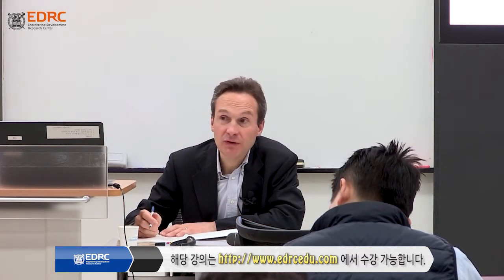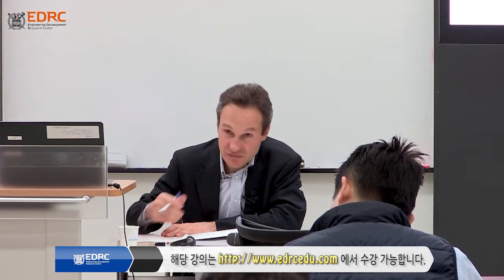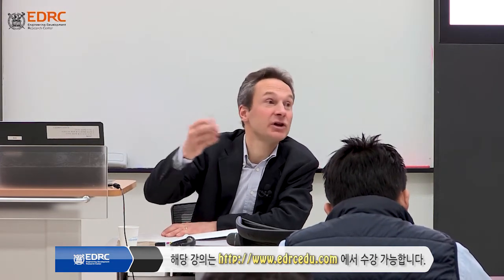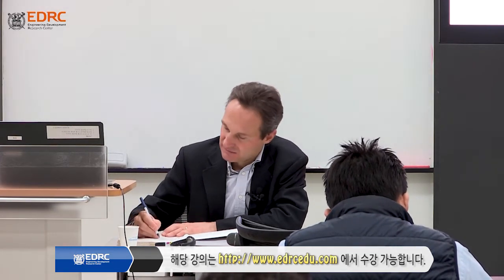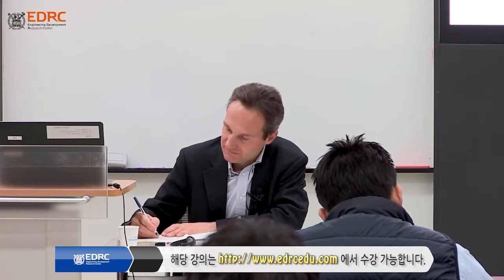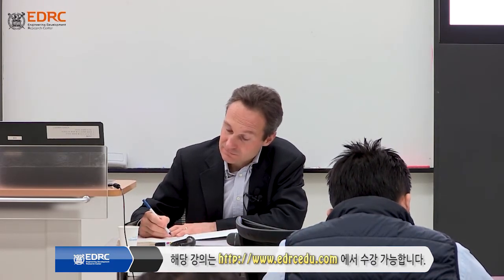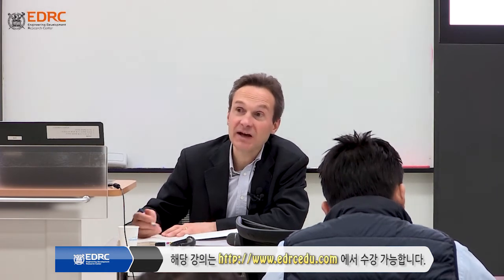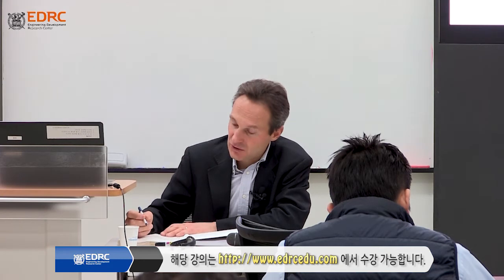If some of you have trouble starting from a blank page, I'll give you one item to get you started. One of the things you need is site conditions - air temperature and so on. Because you need to design items like air coolers, air-cooled heat exchangers. So for this, you need to have the air temperature. Also for the insulation and so on. This impacts a number of items.